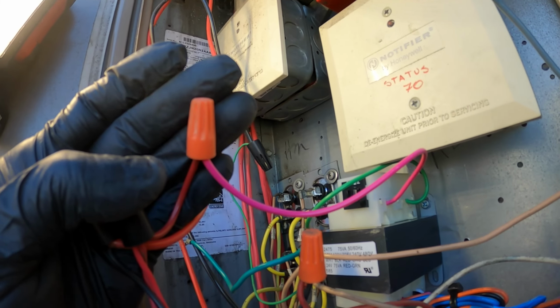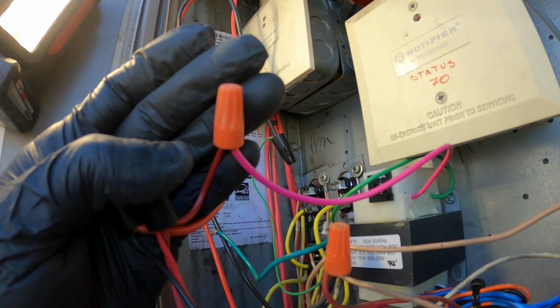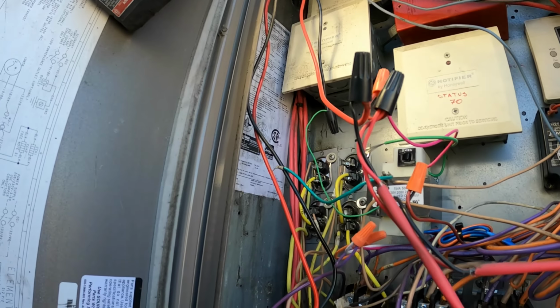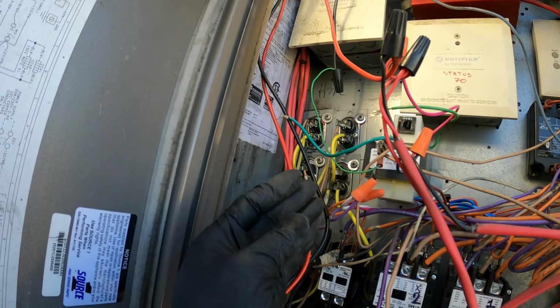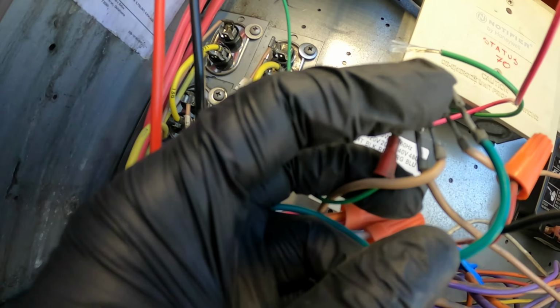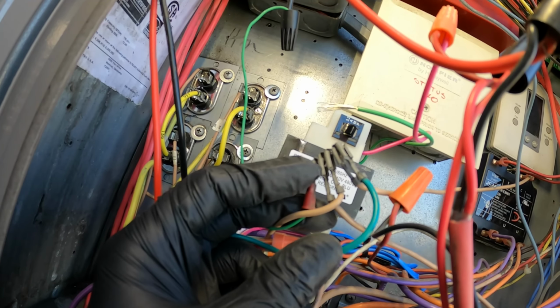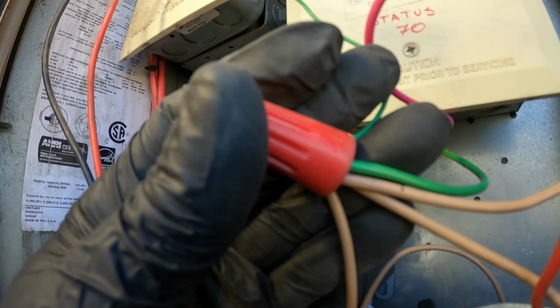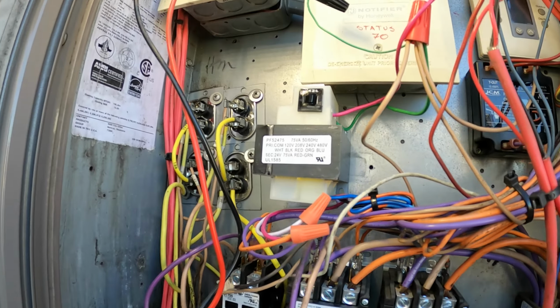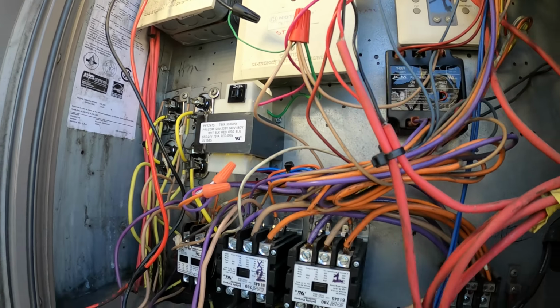So I got one side of the secondary connected to over here like it was before, and my other side, where they don't state which one is common or what, we're gonna go to all these other wires. I'm gonna strip them back and wire nut them in one wire nut. All right, all these wires are now wire nutted there, and we're good to go. You guys got a new transformer.